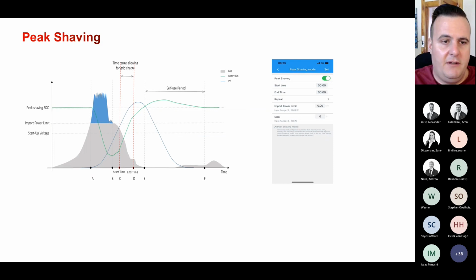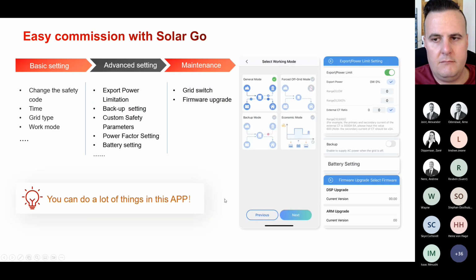As I mentioned, that's peak shaving, so this is especially for our commercial customers. For that kVA demand, where we have that peak demand charge on the utility bill, we can set certain times and operating times for this to operate, and try to limit that usage from the grid from batteries. So you can save a certain amount of battery power for that specifically. The rest of the work modes, as everyone knows, are your general mode, your backup mode, and your economic mode.